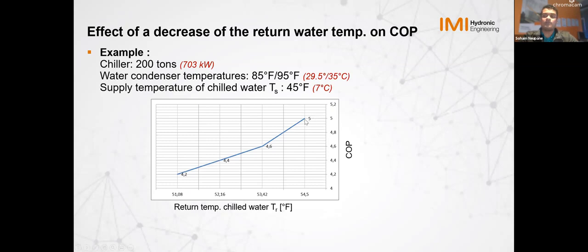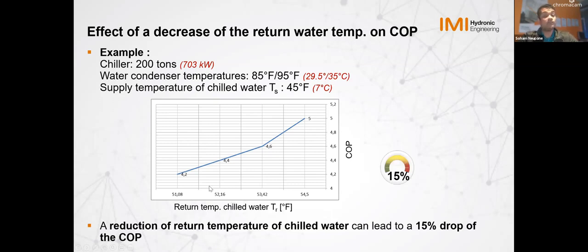So our coefficient of performance was 5, and you see just about 1 degree lower delta T can reduce that efficiency down to 4.6. And from 54.5 to 51.08, you see that there's about a 15% reduction in the coefficient of performance of the chiller. So your chiller is now not as efficient and will be consuming more energy. And it is one of the major sources of energy consumption in any HVAC system.